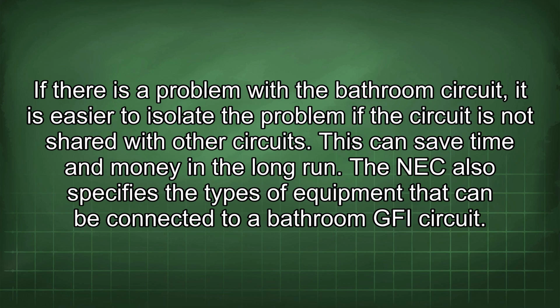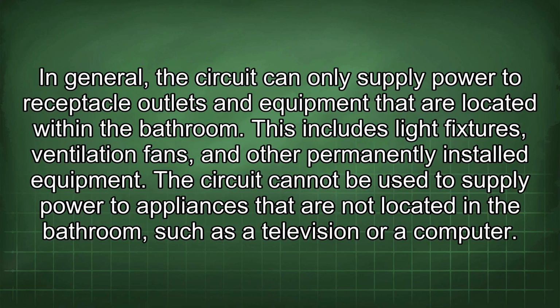This can save time and money in the long run. The NEC also specifies the types of equipment that can be connected to a bathroom GFI circuit. In general, the circuit can only supply power to receptacle outlets and equipment that are located within the bathroom. This includes light fixtures, ventilation fans, and other permanently installed equipment.